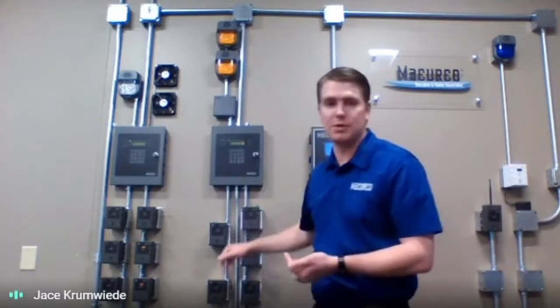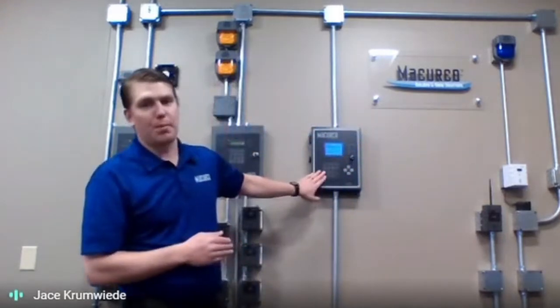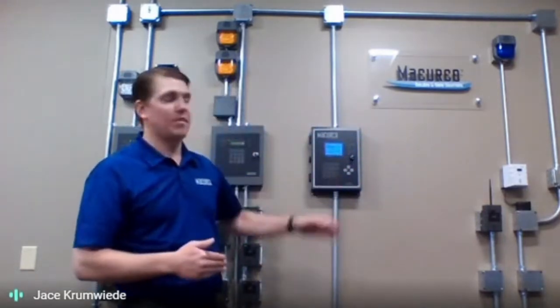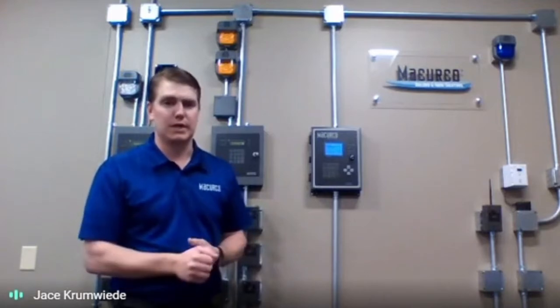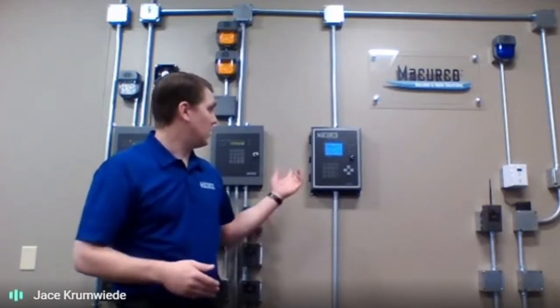Absolutely, yes. So with some of our control panels, you do just have the address. This is address 1. You can add a label onto it, to reference that out in the field. It's accepting up to 99 detectors. With our DVP 1200 control panel, which we just released, you do have up to 192 different detectors, and you also can label those. So if it's northwest corner, anything like that, you can add those labels into that.